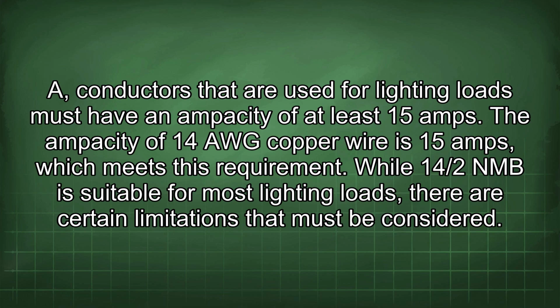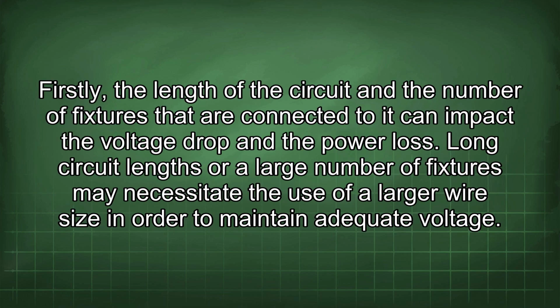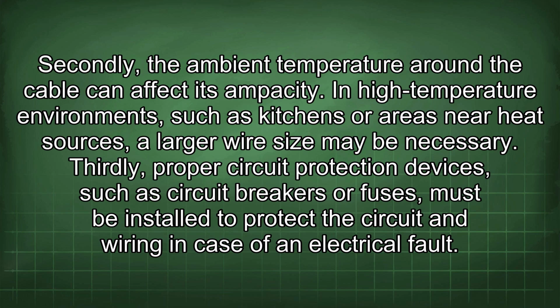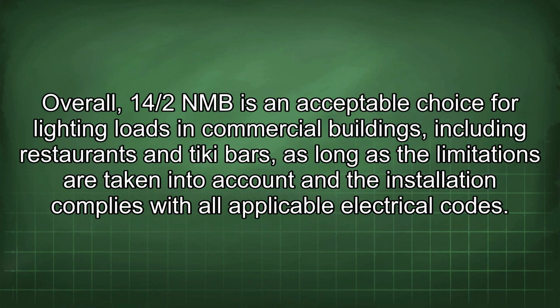While 14/2 NMB is suitable for most lighting loads, there are certain limitations that must be considered. Firstly, the length of the circuit and the number of fixtures that are connected to it can impact the voltage drop and the power loss. Long circuit lengths or a large number of fixtures may necessitate the use of a larger wire size in order to maintain adequate voltage. Secondly, the ambient temperature around the cable can affect its ampacity. In high-temperature environments, such as kitchens or areas near heat sources, a larger wire size may be necessary. Thirdly, proper circuit protection devices, such as circuit breakers or fuses, must be installed to protect the circuit and wiring in case of an electrical fault. Overall, 14/2 NMB is an acceptable choice for lighting loads in commercial buildings, including restaurants and tiki bars, as long as the limitations are taken into account and the installation complies with all applicable electrical codes.